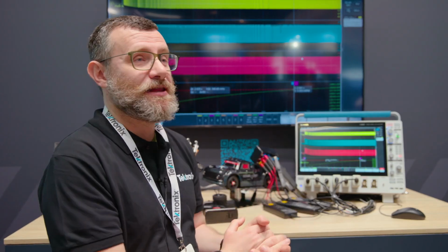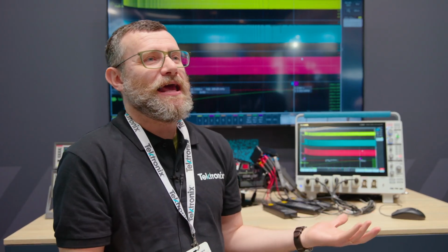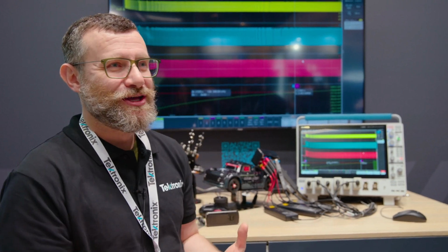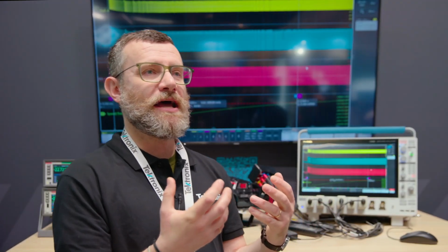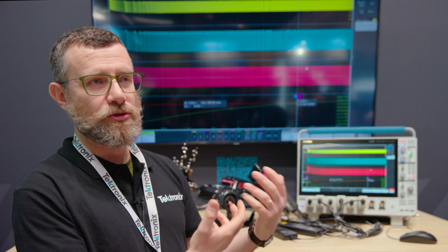Motors, as I said, is one of the key applications for multi-channels. You know, when you test motors, you just don't want to measure the voltages and current. You want to know, for instance, what the speed of the motor is. You want to measure the torque, right? All this data from sensors needs to be acquired and to be related in time with what happens with the voltages and currents. You can really connect your sensors' output to the scope.